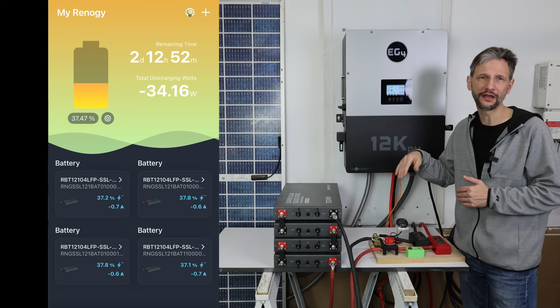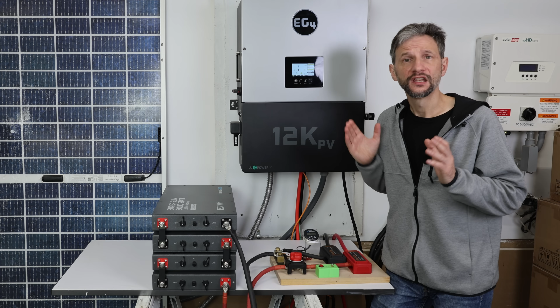I've been running this for a couple of days now. Here's some results on this graph. The battery's charged with solar during the day and then supported my refrigerator and 4-ton AC unit throughout the night. You can see it pulls over 2 kilowatts periodically, completely dwarfing the fridge consumption. By morning, when the sun came out, the batteries were down to about 37% and still almost completely in sync. That combined 5.3 kilowatt hour capacity is enough to run a lot of emergency systems. I mean, it's even running my 4-ton ACs, so that's pretty nice.